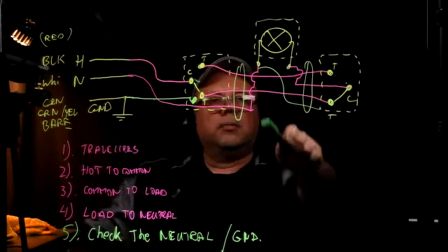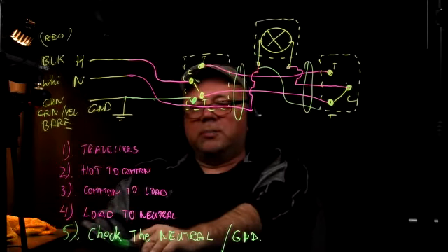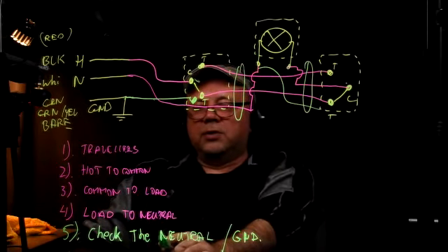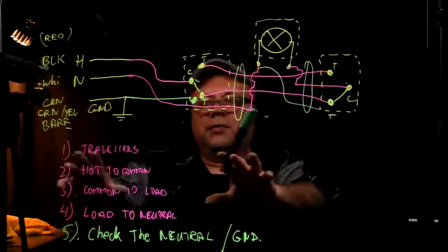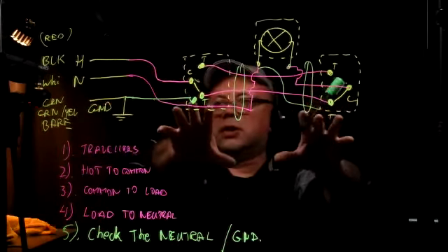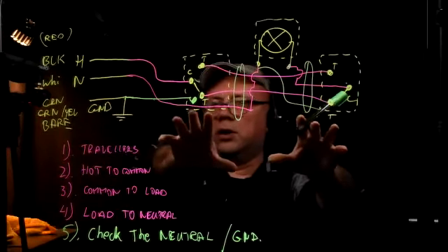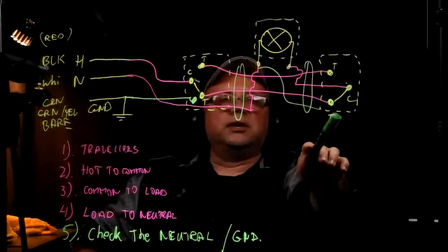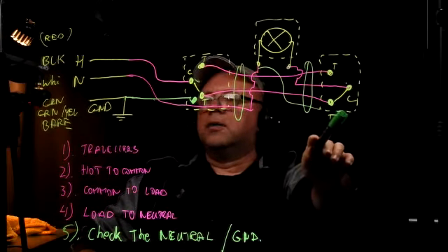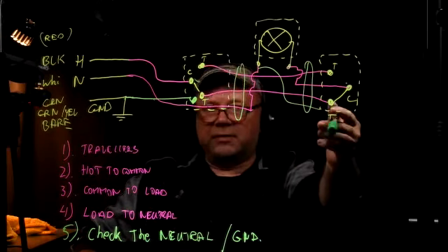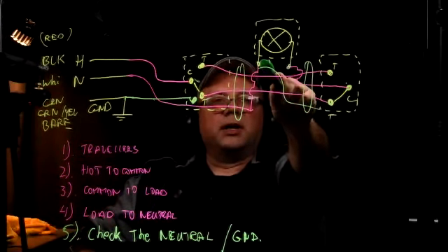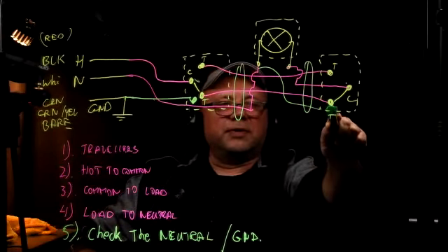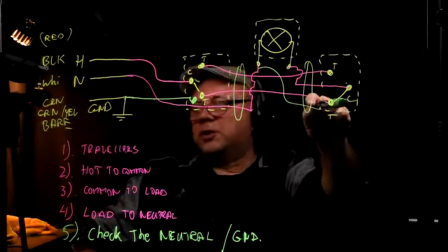Fourth wire here, because we're making sure that the neutral wire is provided to every single box. And when we did the logical connections to make this thing just work, we didn't need the neutral wire to go in there, but we are required to have it there. So that neutral wire from the closest device box is just going to be pigtailed from there, run into this device box, and not terminated.